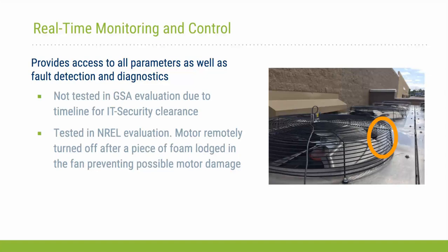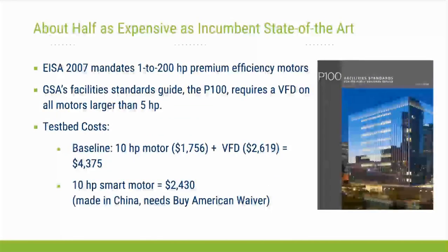However, these capabilities were evaluated in the NREL study, and it proved useful when a piece of foam had lodged itself into one of the condenser fans. So you can see a photo there on the right. In that orange circle is a piece of foam lodged there in the fan. So the remote monitoring capabilities of the smart motor was able to alert the team of a fault occurring, and so the fan motor was remotely turned off to prevent motor damage. Next slide, please.